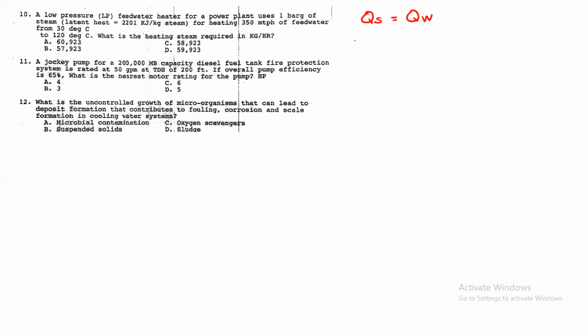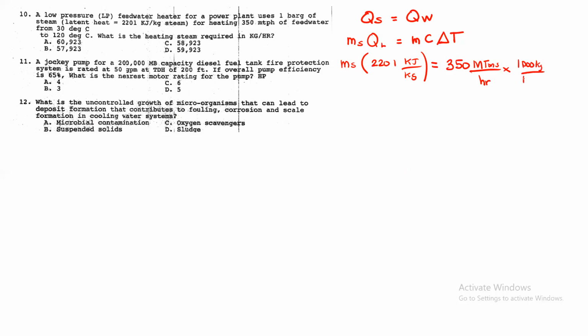So, para makuha natin yung Q ng steam, so mass ng steam times heating value ng steam, heating value or latent heat, QL, is equals to QW. So, MC delta T lang yan. So, MC delta T. So, ganyan lang siya, guys. So, yan yung hinanap natin dito, mass ng steam in kilograms per hour. Then, yung QL natin, so, heating value natin dito is 2201 kilojoules per kilogram is equals to mass ng water, so 350 metric tons per hour. So i-convert natin, so times 1,000 kilogram per metric ton.